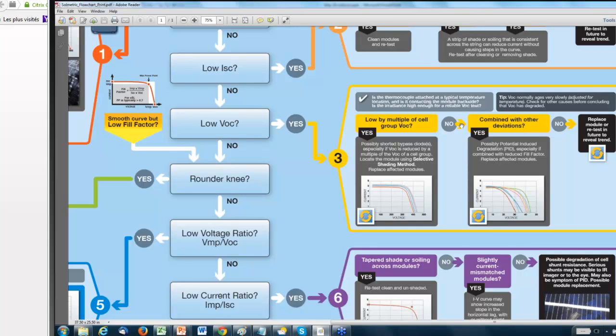If that's not the case, and you're seeing a random distribution of open circuit voltage values that are quite spread, more than temperature variation across the array could account for, especially if combined with other things like a random change in the roundedness of the knee, then there's a good chance you're seeing potential induced degradation. That's too deep a topic for me to go into here, but suffice to say it's an effect involving actual charge migration and ionic migration within the modules themselves, which can be a permanently damaging effect.